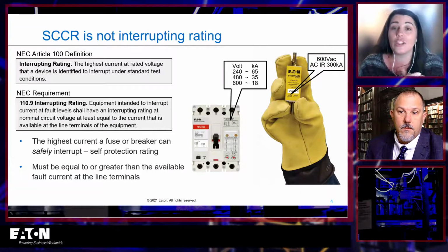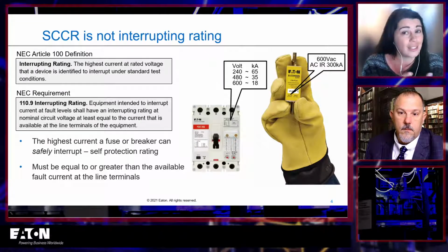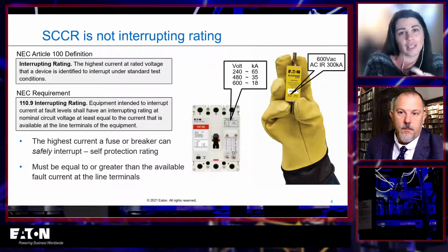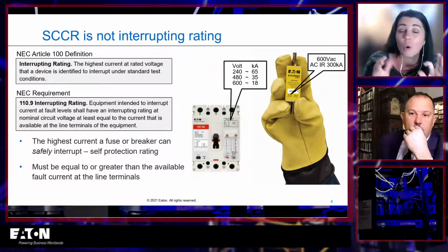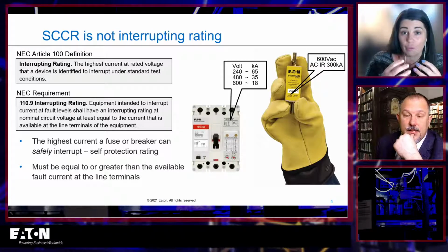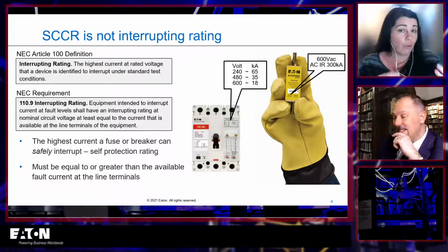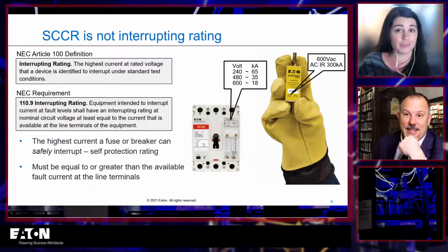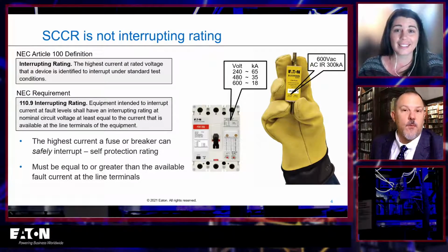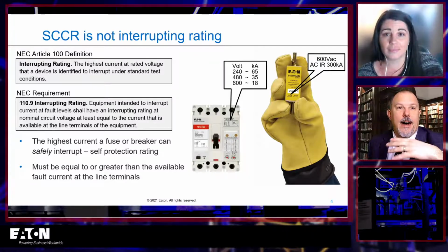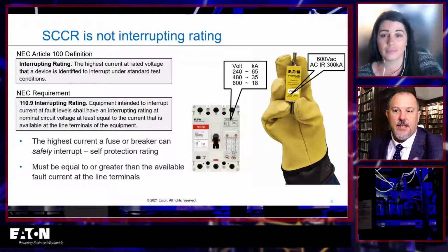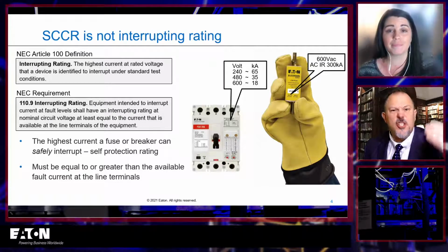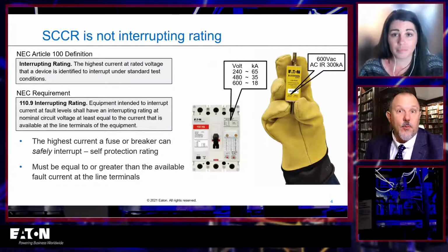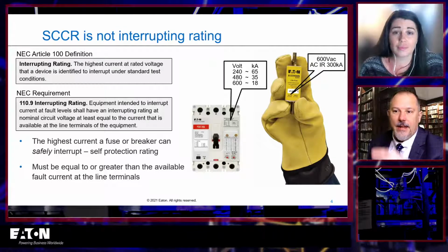We used to use the terminology withstand rating more, and they moved away from that for other reasons, but that's more about what it is. It's trying to withstand however much current it's going to see until an overcurrent protective device opens and protects it. I love the term withstand. I like that better than short circuit current rating because I think people get it better, because interruption is stopping the flow of current, and withstand is being able to withstand the current passing through you, the forces and all that good stuff.